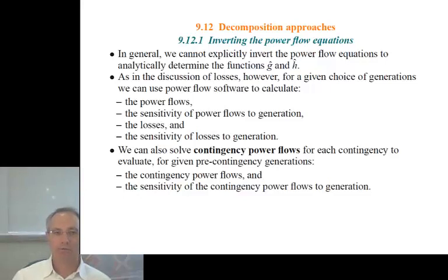Let's look a bit more generally at decomposition approaches to solving power flow. We've already seen and discussed inverting the power flow equations. In general, we can't explicitly invert the power flow equations, but as in the discussion of losses, for a given choice of generations, we can use the power flow software to calculate the power flows, the sensitivity of power flows to generation, the losses, and the sensitivity of losses to generation.